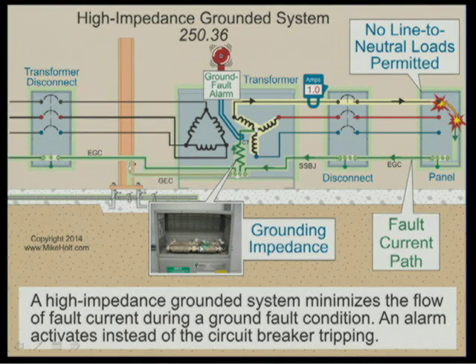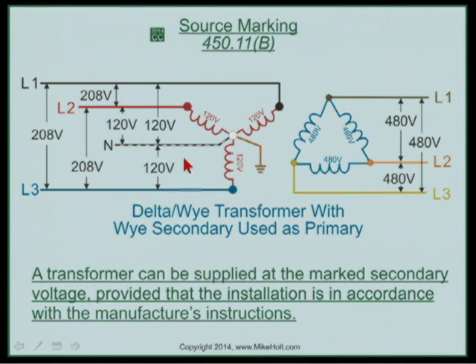Here's your resistor there. The fifth thing I'd like to talk about as it relates to transformers is backfeeding a transformer. That's when you take a transformer that's a 120/208. I'm sorry, that's a 277. No, that's a 480 to 120/208, and you actually backfeed it. Now, let's go through the rules that apply to this. Number one, we have to disconnect this neutral in this graphic because you cannot connect a neutral on the primary side of this Y configuration if you're going to backfeed a transformer. That's all part of the equipment manufacturer's instructions. So that's number one. Number two, the transformer has to be specifically identified as permitted to be backfed.